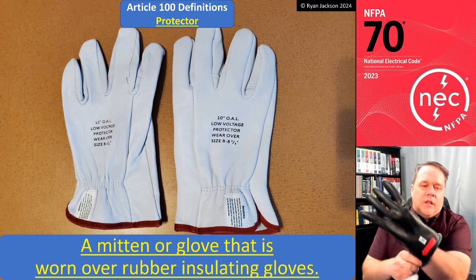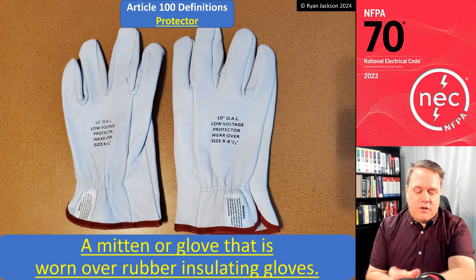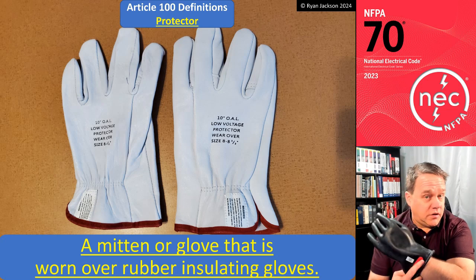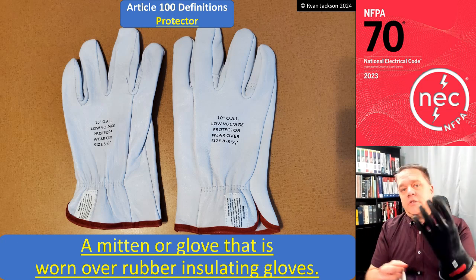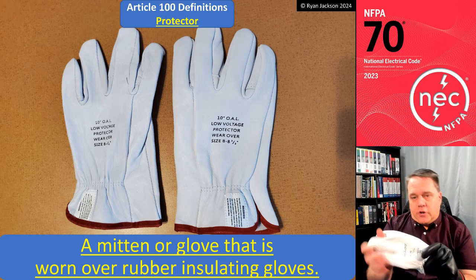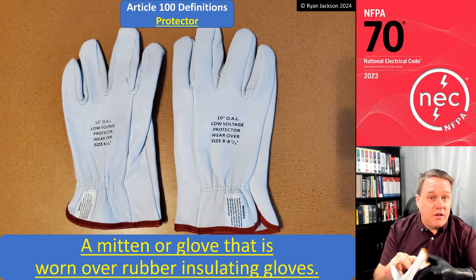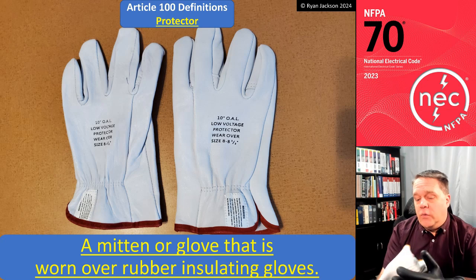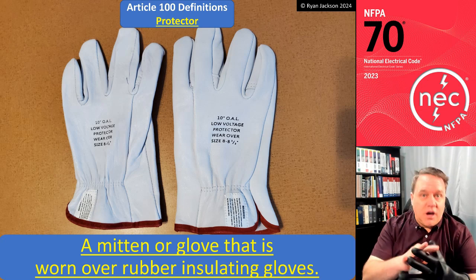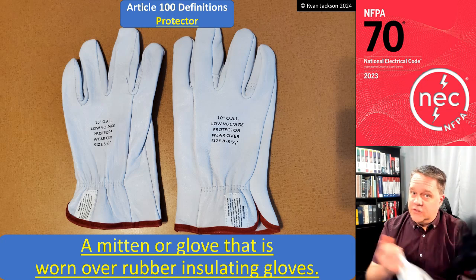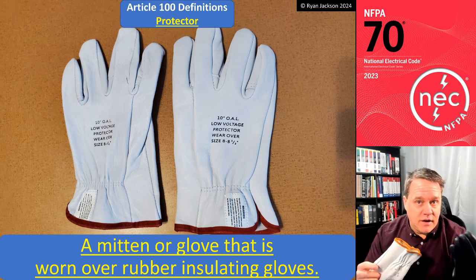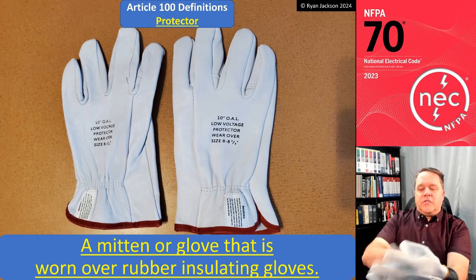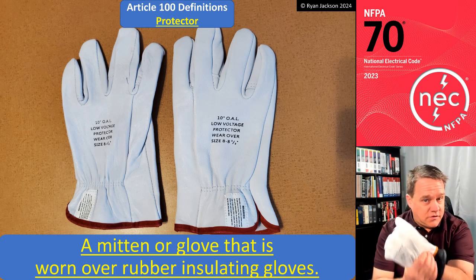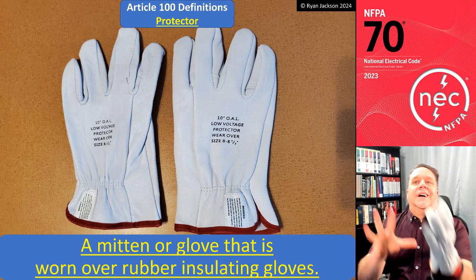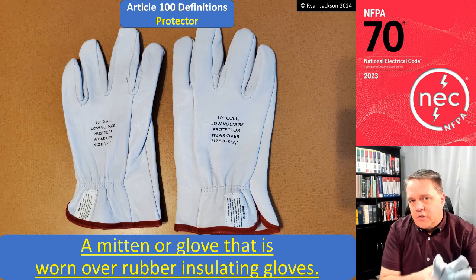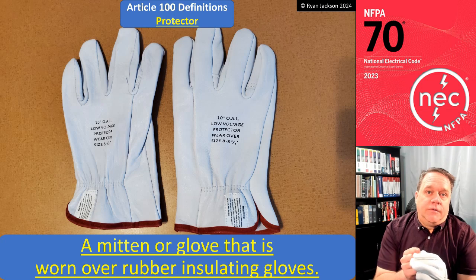All right, so this is your shock protection, right? Your rubber insulating glove. This is the piece of PPE that has a voltage rating, or it's going to have a class 0, 00, what have you. So this is your shock protection. Now, a protector goes over your shock protection, and really it does two things. It protects, but it protects against what? Well, it protects the rubber glove from getting cut up and getting holes poked in it, right? Because if you put a hole in this, then you might as well be wearing bare skin. So it protects the glove, but it also protects you. This is your arc flash protection for your hand. So it can be leather like this, or it can be a different material. So we no longer talk about leather protectors, we just talk about protectors. And we added a definition for them in Article 100.